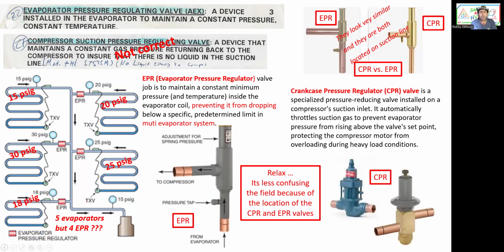The EPR valve's job is to maintain a constant minimum pressure and temperature inside the evaporator, preventing it from dropping below a certain predetermined limit in a multi-evaporator system. What this means is that by controlling the pressure, I control temperature. For example, for air conditioning, there should be 75-degree air in the building. That means coil temperature should be 35. I don't want this coil to be below 35. If it goes below 35, people will be super cold.